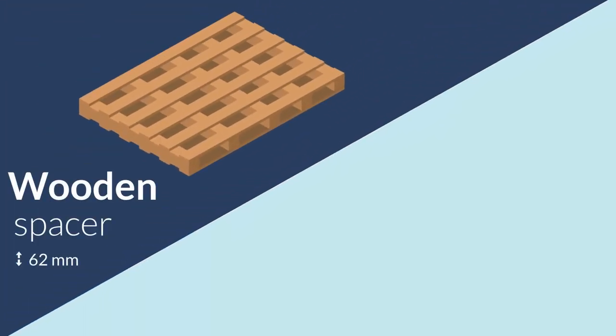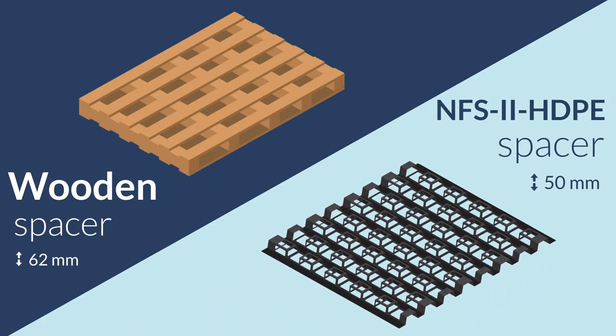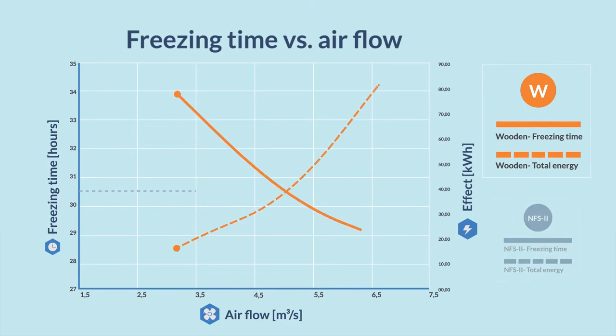We compared some 62mm high wooden freezer spacers with Freezetech's own 50mm high NFS2 HDPE spacers. It is remarkable just how much energy is required to shorten freezing time. Based on a freezing time of 30.5 hours, the wooden spacer required an airflow of 4.75 m³ per second and 39 kWh of energy. The airflow with Freezetech's NFS2 spacer could be reduced to 2.9 m³ per second, which reduced the energy consumption to 19 kWh — a 50% saving under identical conditions.